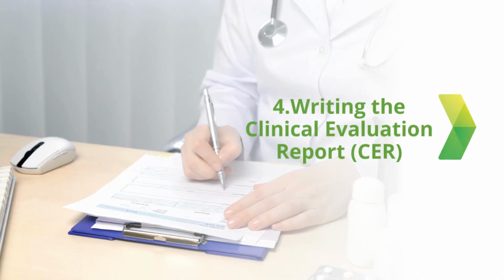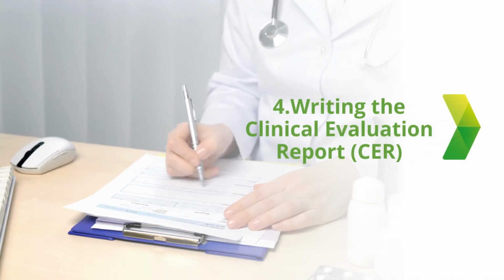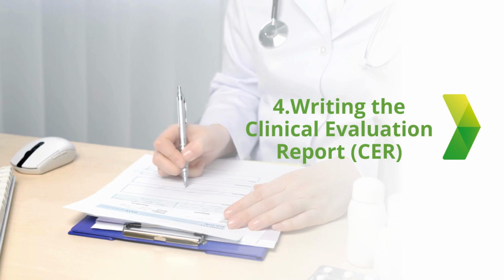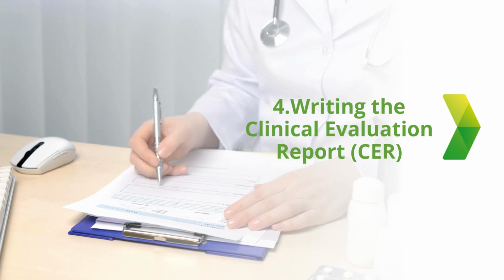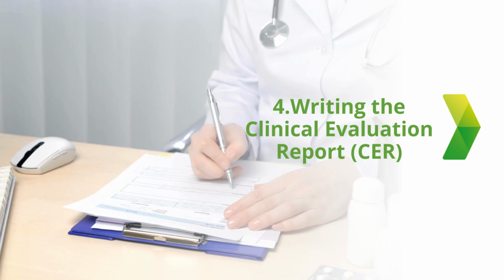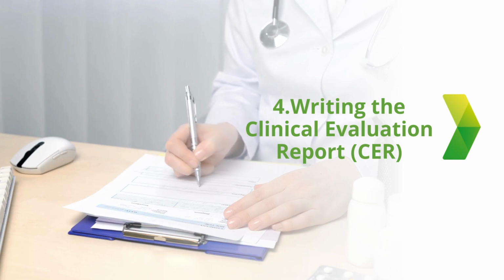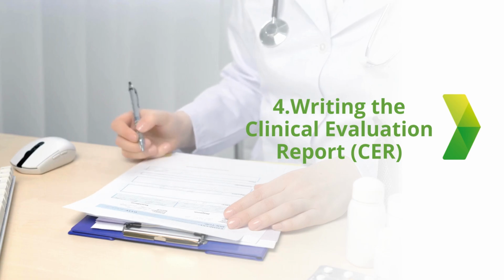4. Writing the Clinical Evaluation Report, CER. All findings are compiled in the Clinical Evaluation Report. The CER includes an analysis of all collected data, any identified risks, and how the device complies with the general safety and performance requirements under MDR Annex 1.